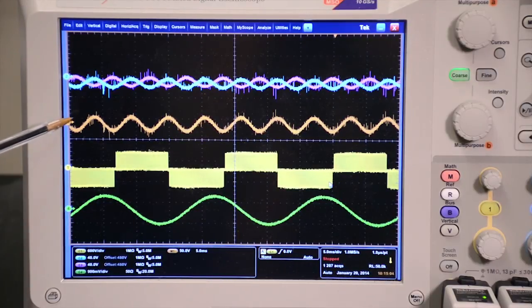The blue and purple curves are the DC link capacitors for the neutral point DC link, and this is the neutral point voltage imbalance. You can observe a large voltage ripple on the DC link capacitors and also the neutral point voltage without balancing.